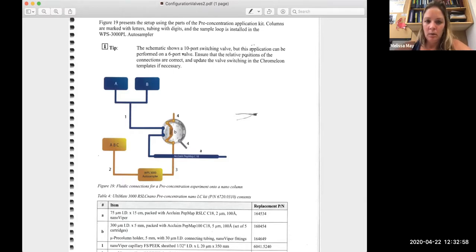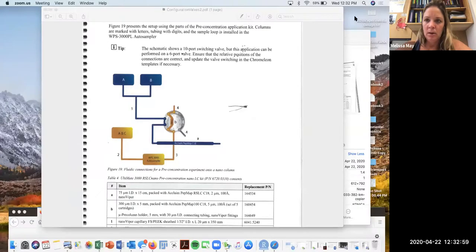The flow path from loading buffer through the autosampler: instead of having a trap column there, basically you take that whole thing out of line and you can just load things directly onto your analytical column. We typically don't do that because our samples are messy. But if you had a purified sample, that would probably be a preferred route because you lose less of your sample by doing it. So you have one less step where things could basically go wrong.